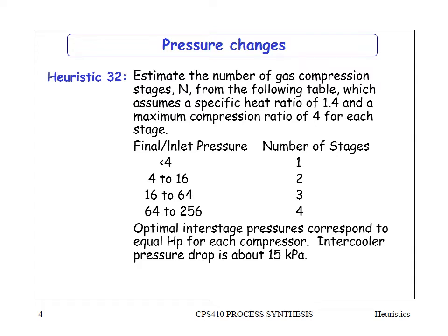This also refers to a specific heat ratio of 1.4, which is normal air. That specific heat ratio is important because it describes the isentropic temperature rise as you compress the gas. The higher the gas temperature rises when compressed, the more stages you will need. An example is the compressor from the Aspen tutorial, where the temperature rose to 1200 degrees without using interstage cooling.